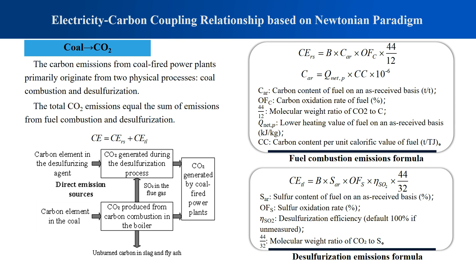In the first box, once lower heating value and efficiencies are specified, generation power can be approximated as kBE times coal consumption. In the second box, the carbon dioxide mass emission rate can be approximated as kBC times coal consumption. kBC includes the combustion carbon term and the desulfurization term. Dividing the carbon side coefficient by the electricity side coefficient eliminates coal consumption. The bottom formula states that the real-time carbon dioxide mass emission rate equals KEC times real-time generation power.